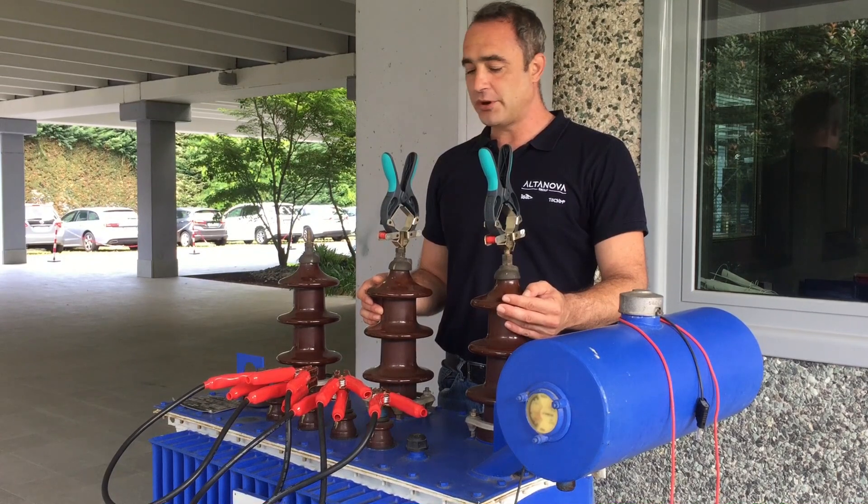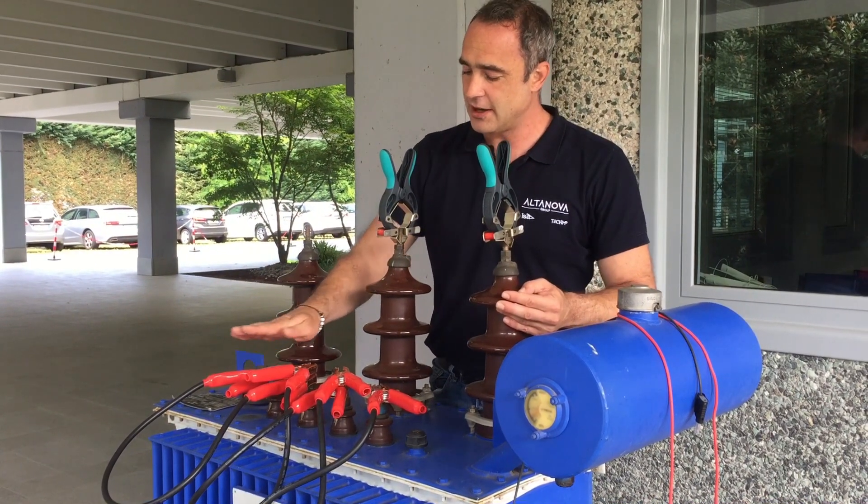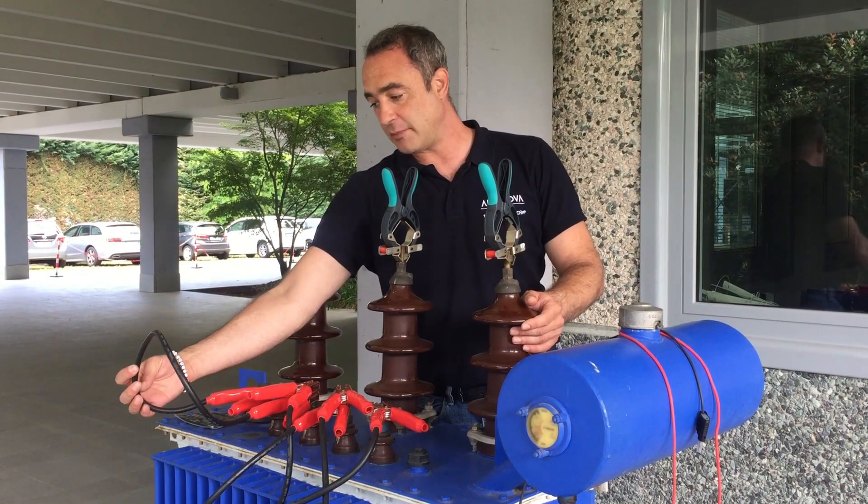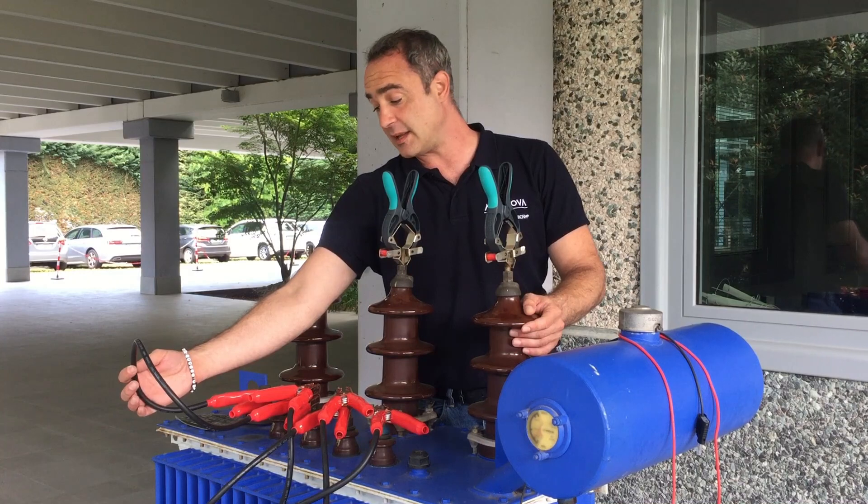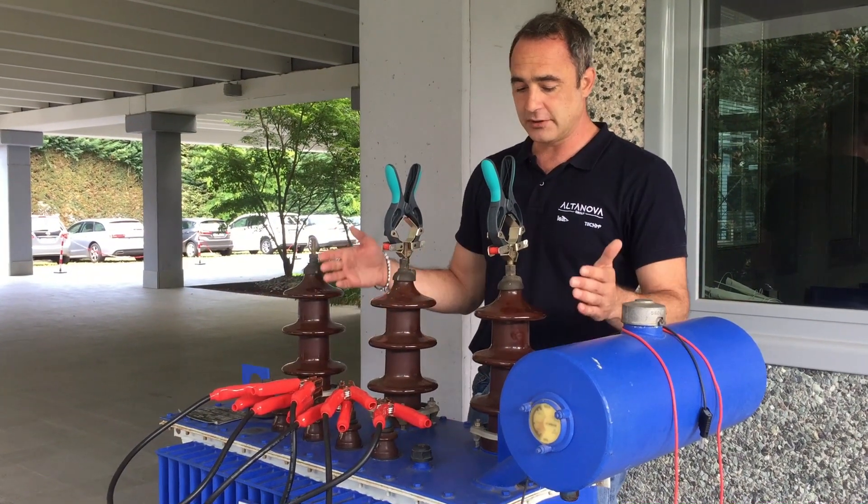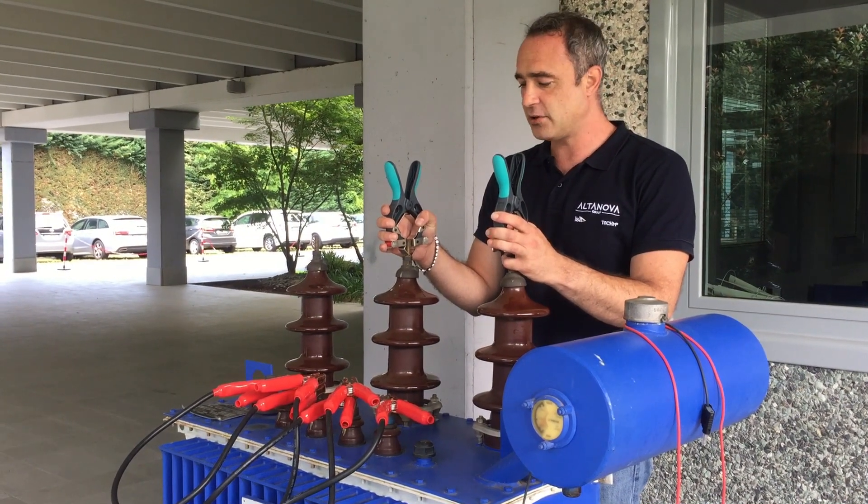Now what is important in this test? It's important of course to correctly short circuit the secondary side because the currents passing through here might be quite big, maybe a few tens of amps, and also it is important to correctly connect the whole test. So let's start with the connections.